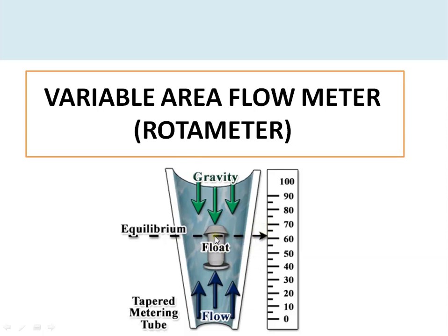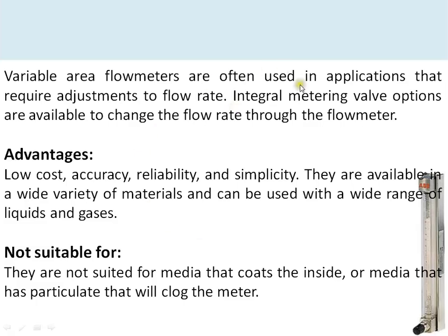The position of the float is clearly visible from outside the rotameter. In applications where the transparent glass tube cannot be used — because the operating pressure may be high, or the moving fluid may not be compatible with glass — metal tube rotameters are used. In a metal tube rotameter, the position of the float is not visible to the operator; instead, the movement of the float is transferred to an indication using a magnetic and mechanical arrangement.